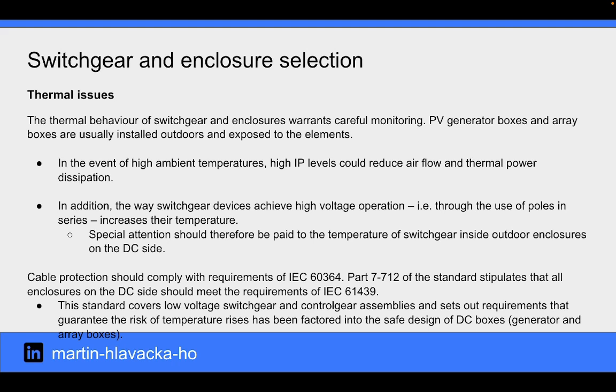Cable protection should comply with requirements of IEC 60364. Part 7-712 of the standard stipulates that all enclosures on the DC side should meet the requirements of IEC 61439. This standard covers low voltage switchgear and control gear assemblies and sets out requirements that guarantee the risk of temperature rises has been factored into the safe design of DC boxes.